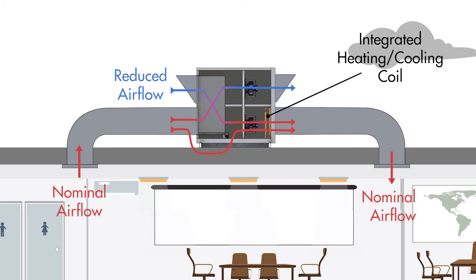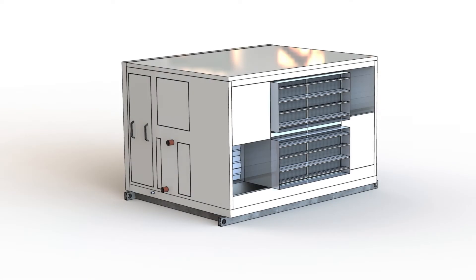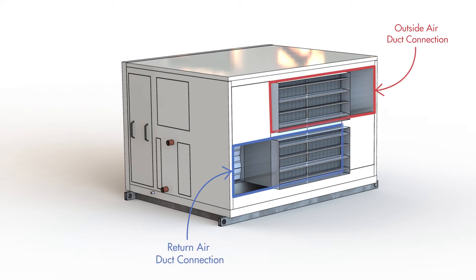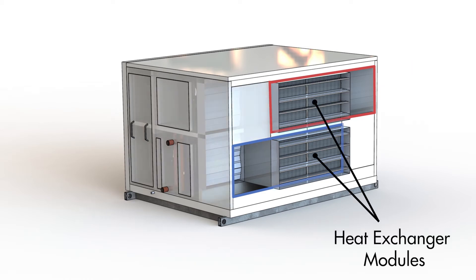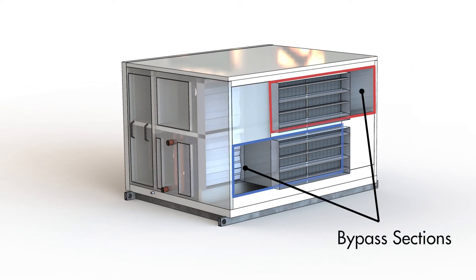Instead, recirculated air needs to be introduced to make up for any reduction in outside air and keep the supply air volume constant. And adding this recirculated air through an ERV or HRV unit requires heat exchanger bypass. To explain how return air can bypass an air-to-air heat exchanger in return air bypass mode, here is a suction side view of an ERV or HRV unit. This blue outline shows the return air duct connection, while this red outline shows the outside air duct connection. These duct connections encompass the heat exchanger modules and the bypass sections.